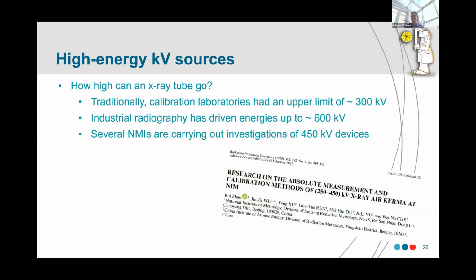And what we're seeing today is a push beyond that 300 kV limit. Vendors will produce tubes for industrial radiography up to about 600 kV at the moment, and several NMIs are carrying out investigations up to about the 450 kV level. Now, of course, we've got to keep in mind 450 kV is still only sort of 220 to 250 keV photon energy. We're still at the low end of the spectrum, but it's beginning to push upwards.